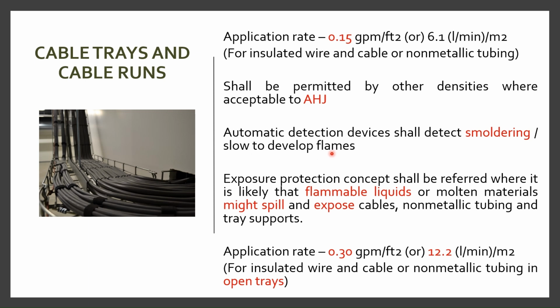So the exposure protection concept shall be referred to where it is likely that flammable liquids or molten materials might spill and expose these cables, non-metallic tubing and tray supports. In that particular case, we need to consider the application rate as 0.30 GPM per square feet. So here I mentioned this is for insulated wire and cable or non-metallic tubing in open trays. These things we need to remember when we design the cable tray protection with a water spray system.